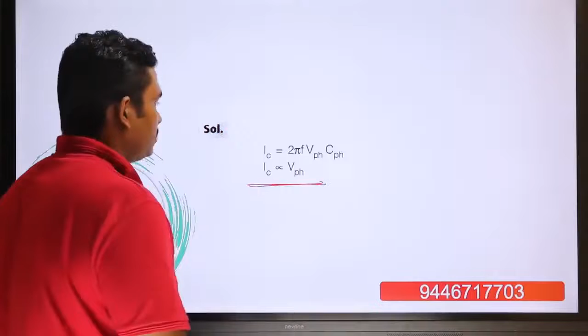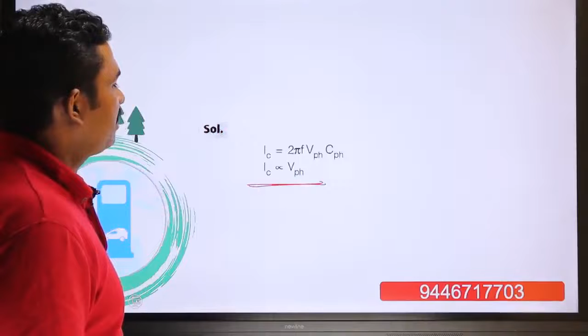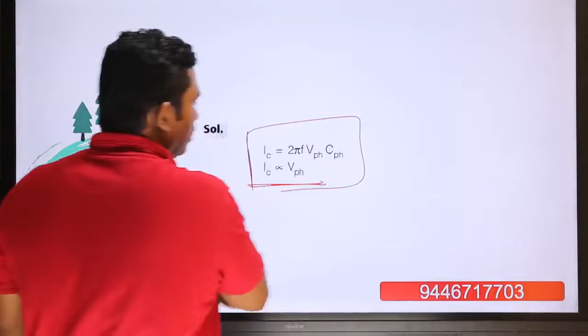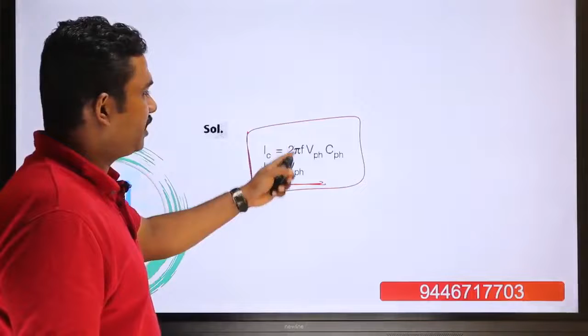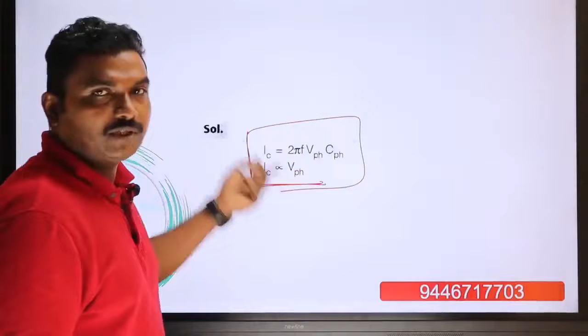Question 4: the charging current of a 400 kV transmission line is more than that of a 220 kV line of the same length — true or false? Charging current is proportional to phase voltage, so for a 400 kV system the phase voltage is higher than for a 220 kV system. Therefore the statement is true, since IC = 2·π·f·V_phase·C_phase, meaning IC is proportional to V_phase. As phase voltage increases, charging current also increases.